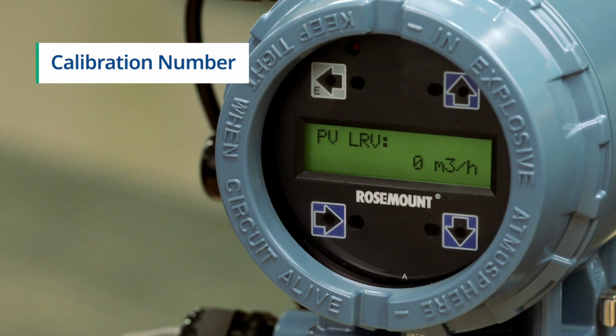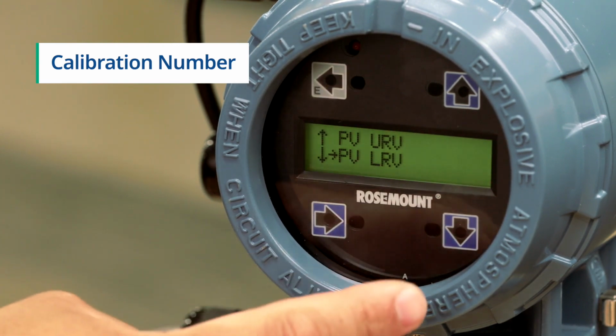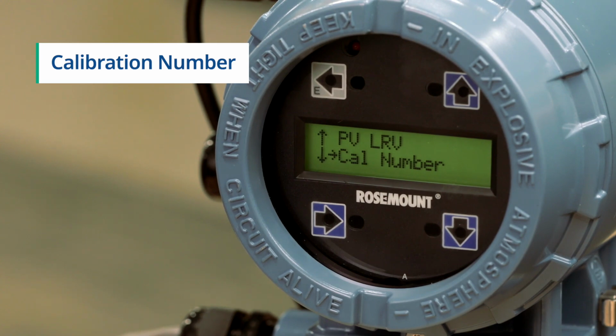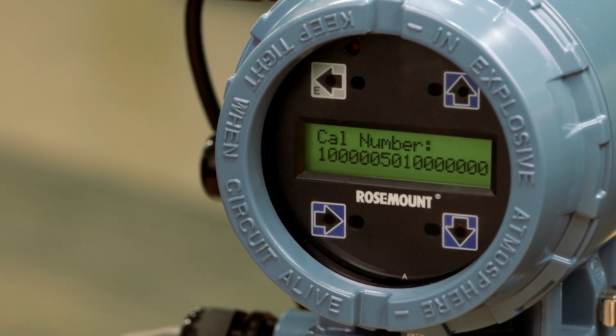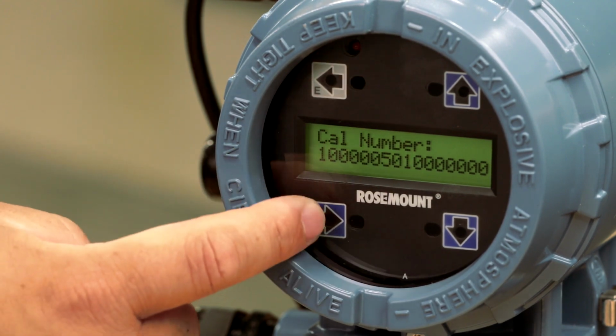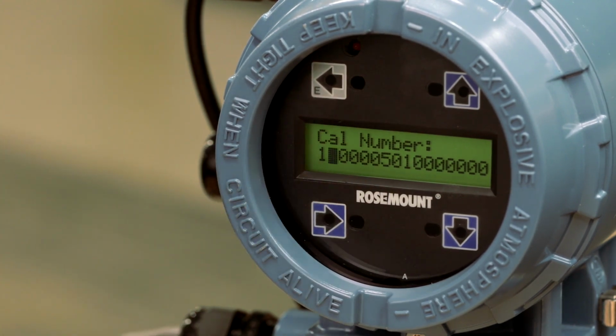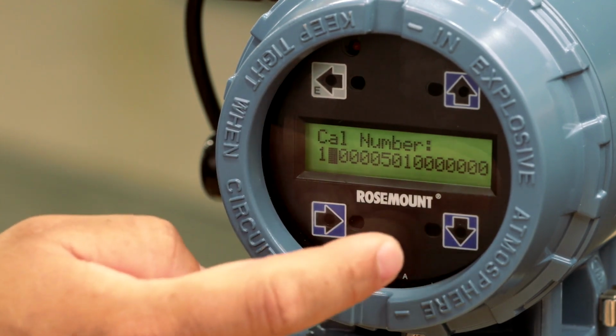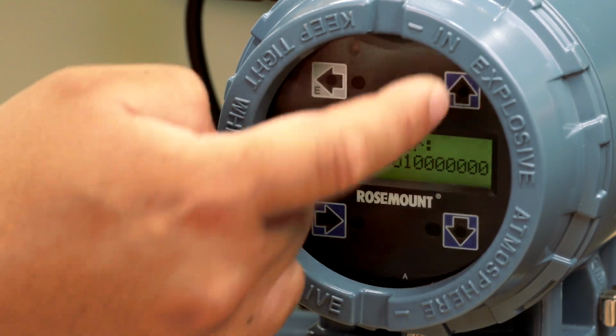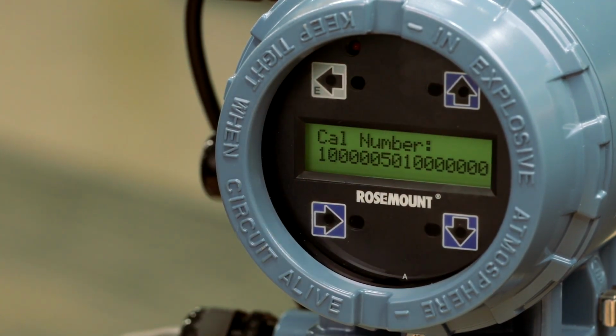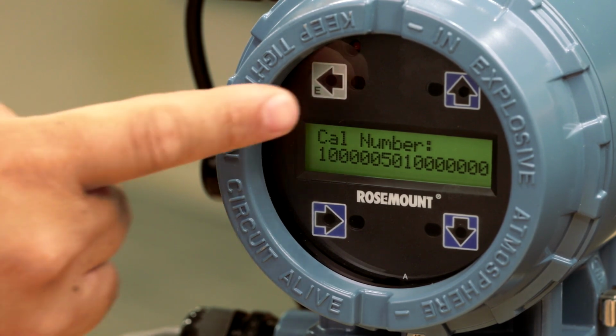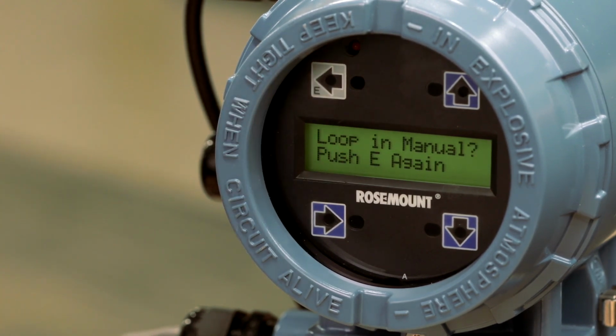Next, we will input the calibration number. The sensor calibration number is found on the sensor nameplate. To enter the calibration number, press the E button to navigate back to the basic setup screen. Then press the down arrow to scroll through the menu options, and press the right arrow to select calibration number. Press the right arrow to move the cursor to the place value that needs to be changed, and press the up and down arrows to increase or decrease the value. When the CAL number value is entered properly, press the E button to select the value. Finally, press the E button again to save your selection.